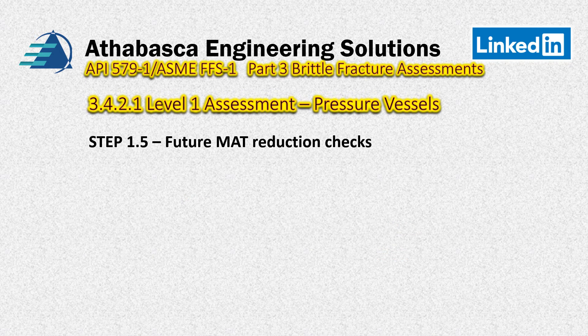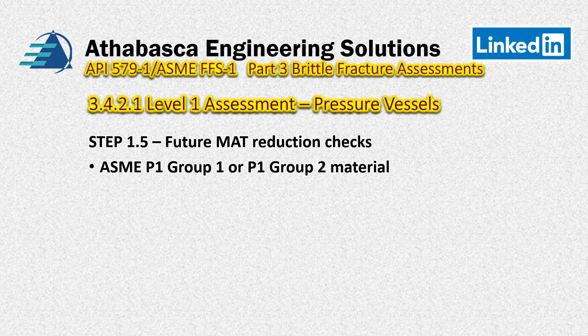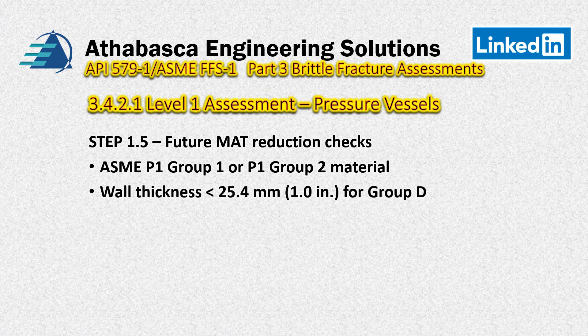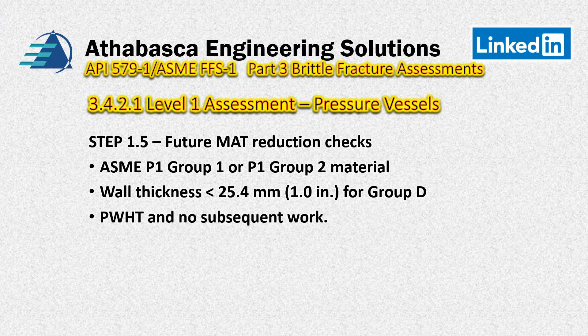We're going to look at step 1.5, future MAT reduction checks, so we can use our curve and then continue. These are some of the restrictions: it has to be an ASME P1 Group 1 or P1 Group 2 material, which is basically your carbon steel material, in order to be considered. Your wall thickness has to be less than one inch for Group D materials, and the post-weld heat treatment has to be done with no subsequent work based upon that.